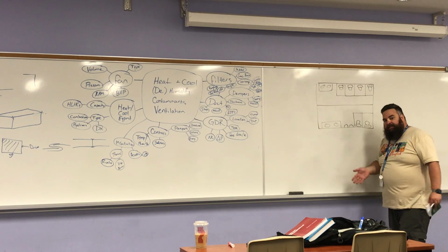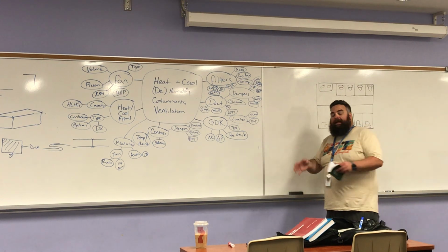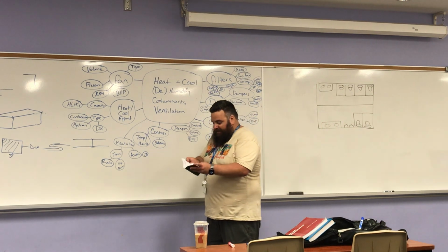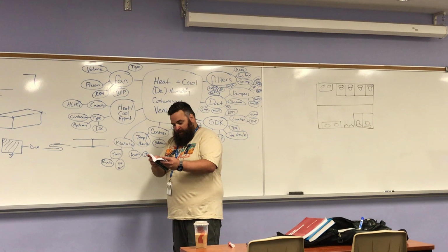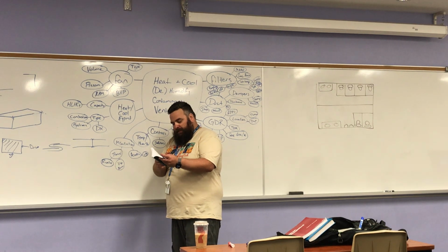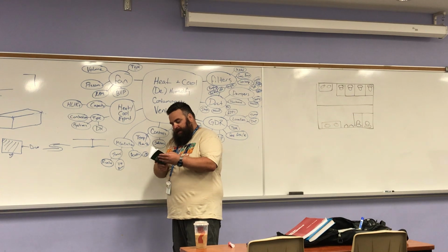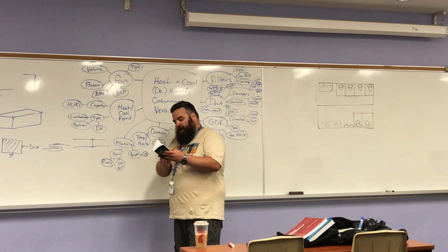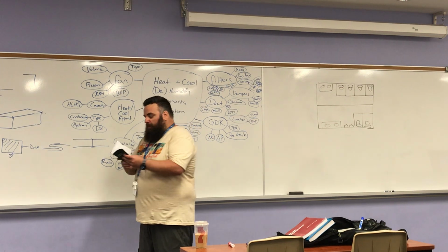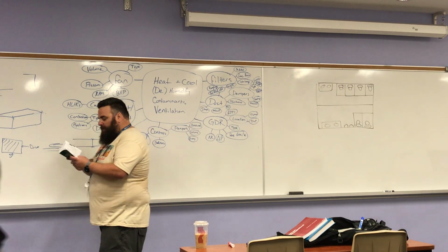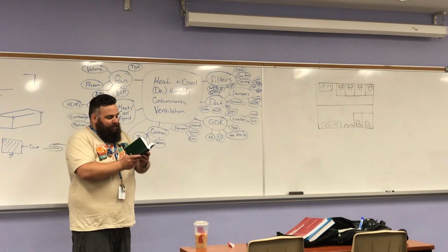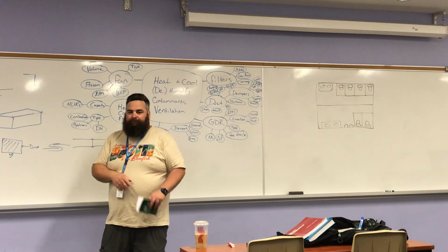So 50 CFM / 70 CFM and class 2 air. The distinction between the 50 and the 70 in the notes here is E&H. Rate is for toilet room intended to be occupied by one person at a time. Oh, sorry, that's private. Rate is per water closet, urinal, or both. Provide the higher rate where periods of heavy use are expected to occur. The lower rate shall be permitted to be used otherwise.